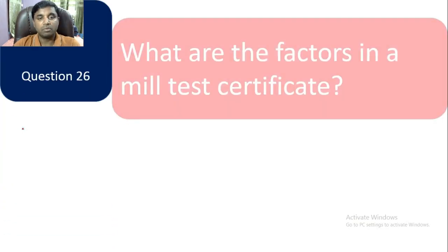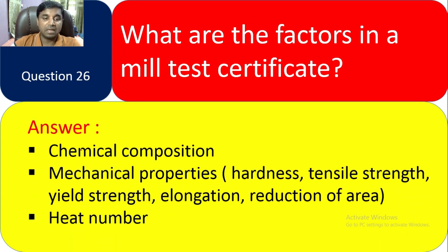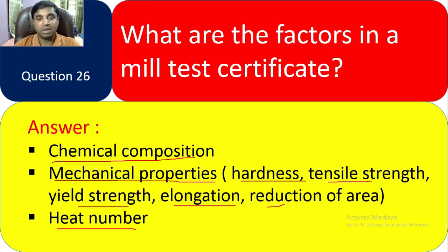Question 26: What are the key factors in a mill certificate? The important factors are: chemical composition, mechanical properties (hardness, tensile strength, yield strength, elongation, reduction of area), and heat number. All these must be checked against the applicable standard.